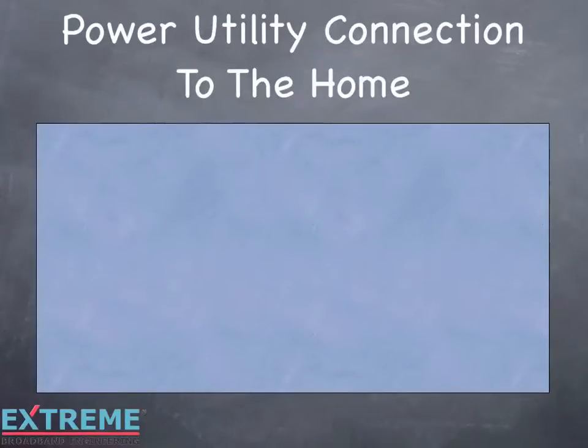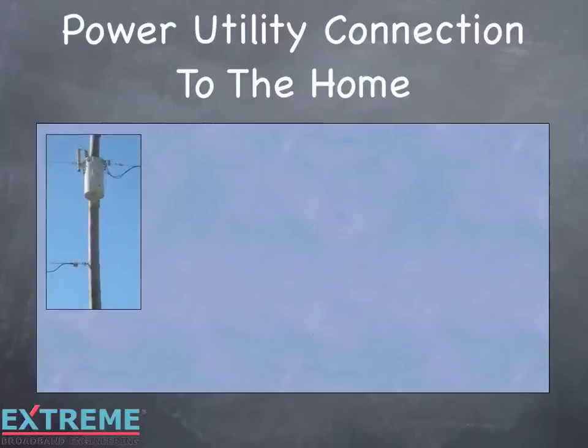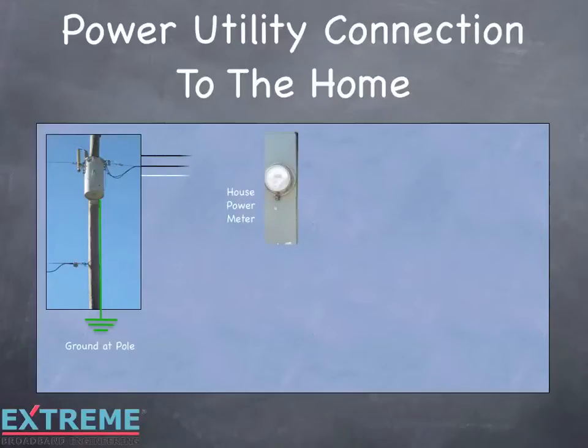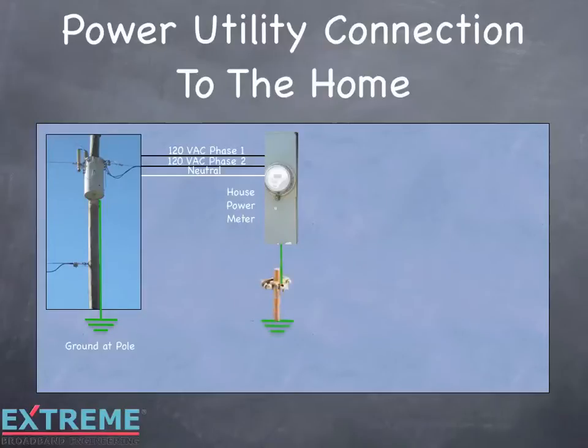Before we talk about the drop isolator, let's take a look at how the power utility is connected to the home. At the pole is a power transformer that converts the high line voltage down to 240 volts AC, which will be used in the home. At each transformer a ground is established, and at the house is a power meter. From the power transformer to the power meter are two 120 volt AC lines at different phases, and one neutral line used for the power return path. The neutral line is bonded to the power ground. At the power meter, the power utility establishes a ground, which provides safety by taking any faults to ground and also provides a ground reference.